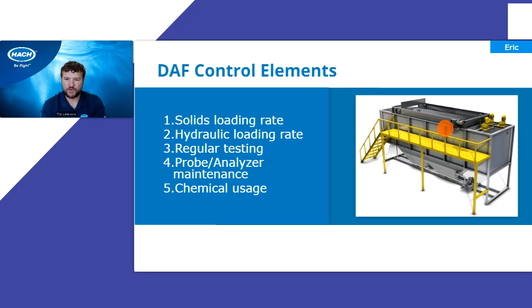When it comes to control aspects of a DAF, there's a few things to consider. First is your solids loading rate. So how much solids are coming into that tank to be processed or treated. There's the hydraulic loading rate. So how much flow is actually coming into the tank, which both need to be controlled to really ensure that you're having good quality effluent coming out of the DAF itself. Regular testing. So if you do have a DAF, how are you controlling that? Is it simple grab samples? Is it visual management? Or is it inline probes to help you automate that process, which we'll talk about shortly? So maybe you're using inline probes, pH, TSS probes, etc.